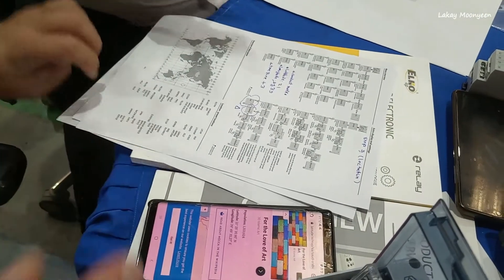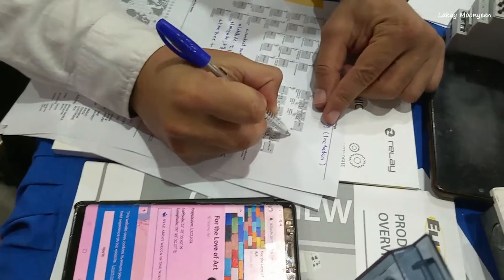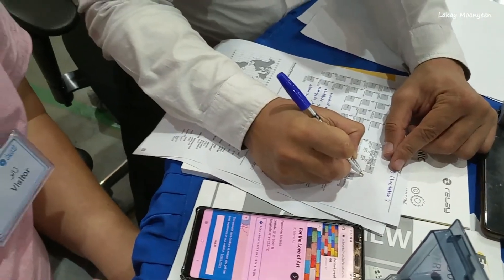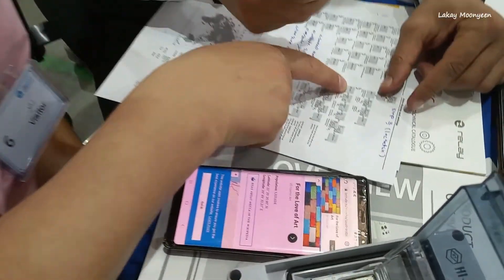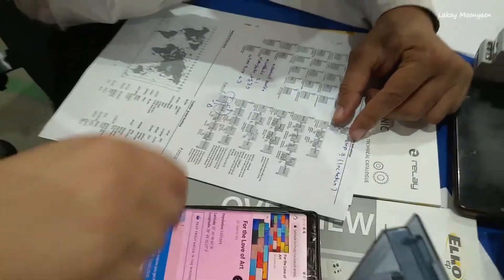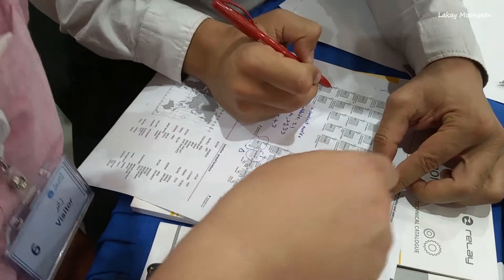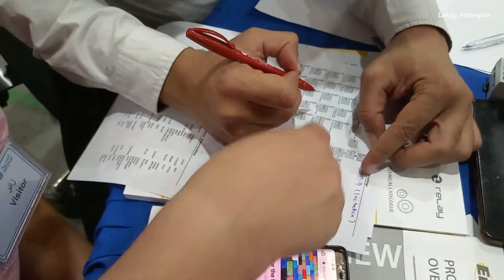Three steps done. Now Step 4 is Verification — it's basically a commissioning check. Write 'Verification' here. There are two verification steps: Verification Step 1 and Verification Step 2. I recommend doing both. If you make only Verification Step 1, it will verify the switching on and off times, but if you forgot 'No Summer Winter,' you will not find out. You will only find out if you make Verification Step 2.